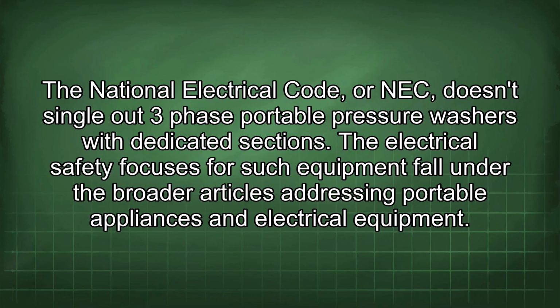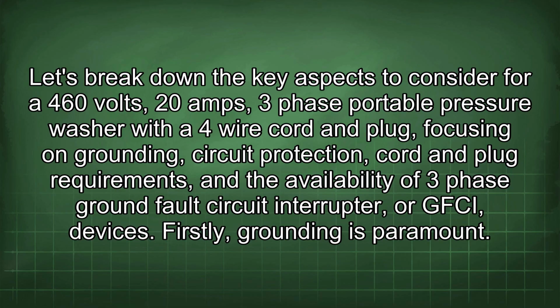The National Electrical Code, or NEC, doesn't single out three-phase portable pressure washers with dedicated sections. The electrical safety focuses for such equipment fall under the broader articles addressing portable appliances and electrical equipment. Let's break down the key aspects to consider for a 460 volts 20 amps three-phase portable pressure washer with a 4-wire cord and plug, focusing on grounding, circuit protection, cord and plug requirements, and the availability of three-phase ground fault circuit interrupter, or GFCI, devices.